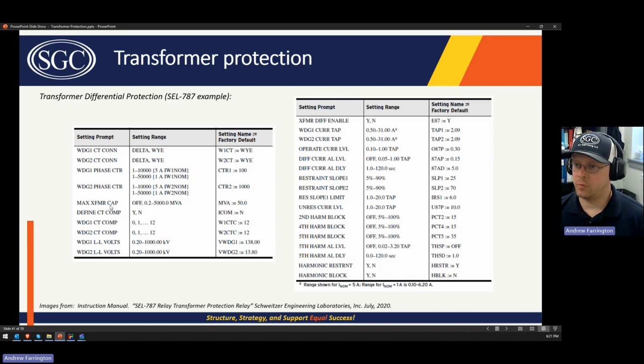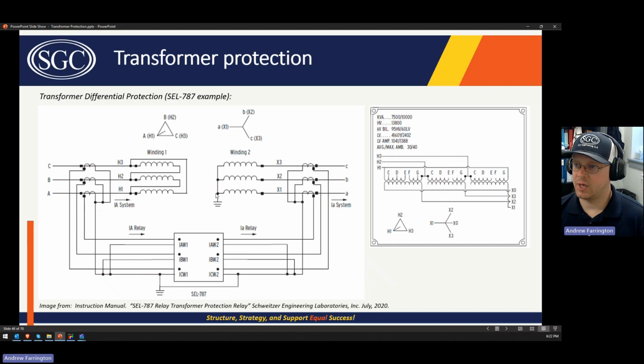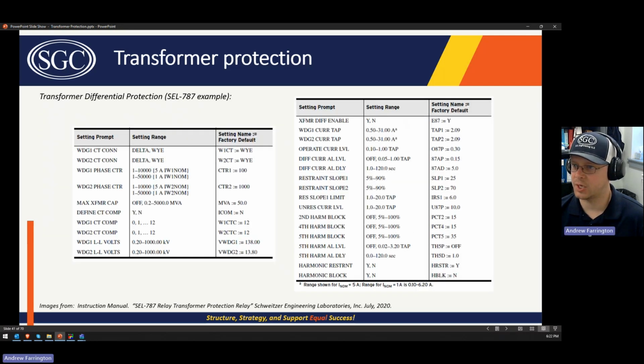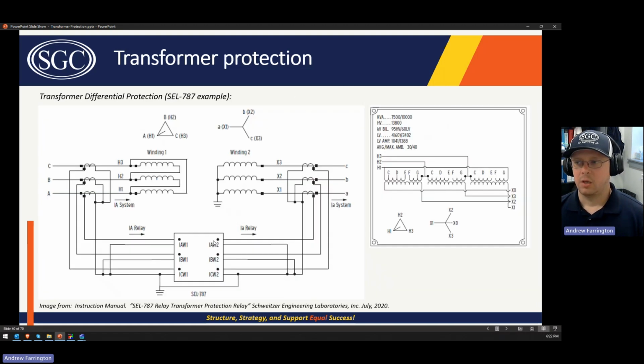Then you've got the transformer's maximum capacity in MVA. So you'd go to the nameplate and look at the maximum transformer rating, which is 10 MVA. So that's what you'd set that setting to. Then this setting here is whether or not you need to define the CT compensation, yes or no. Generally, you're going to have to set that to yes. And what that means is that the currents that are seen by each CT cannot be directly related by the relay without some sort of compensation.